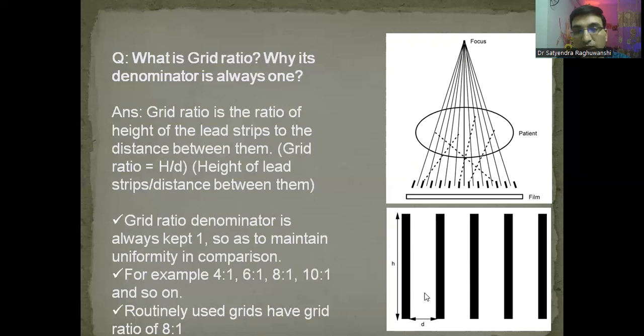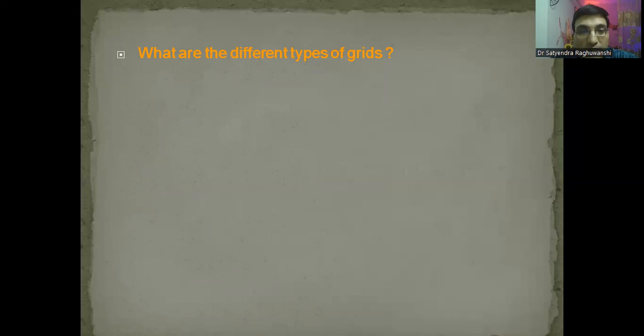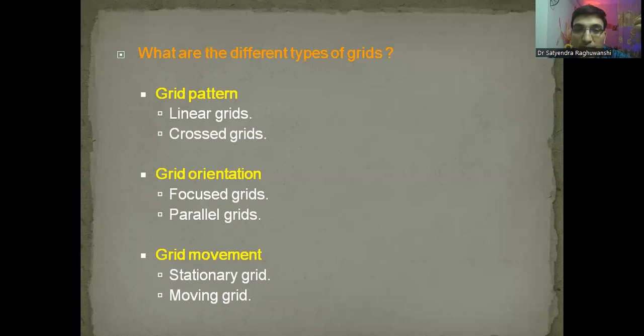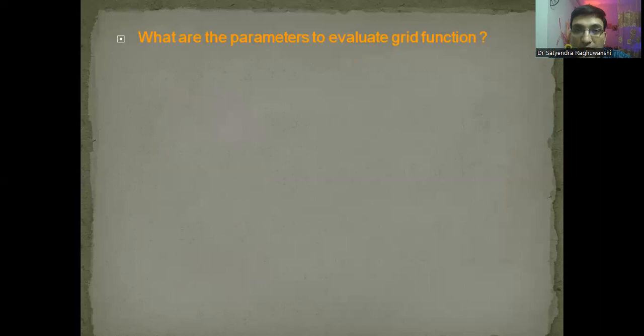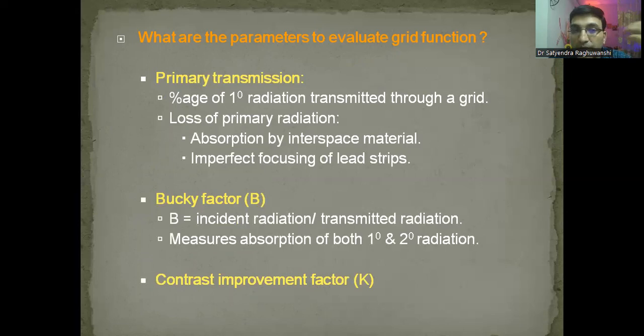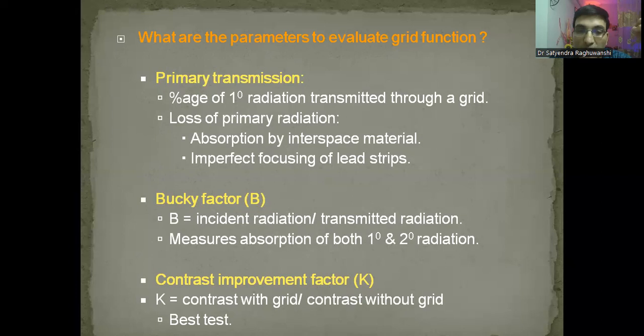Then he might ask: what are the various types of grids? Grids can be divided by grid pattern, grid orientation, and grid movement. Based on pattern: linear or cross grids. Based on orientation: focused or parallel grids. Based on movement: stationary or moving grid, also known as Bucky. How do you evaluate grid function? Remember as PBC: Primary transmission — percentage of radiation transmitted through the grid; Bucky factor — incident radiation upon transmitted radiation; and Contrast Improvement Factor — ratio of contrast with grid upon contrast without grid, since the grid improves contrast.